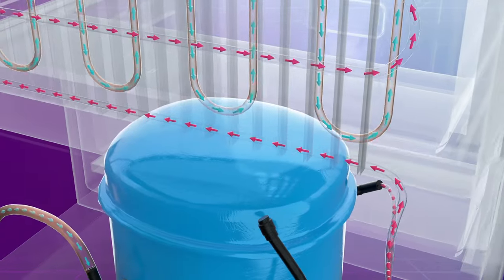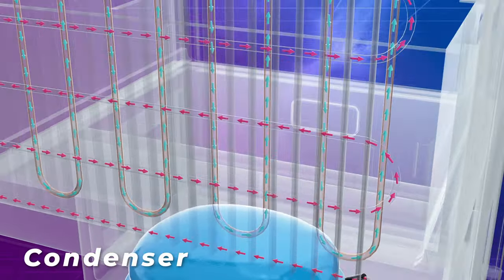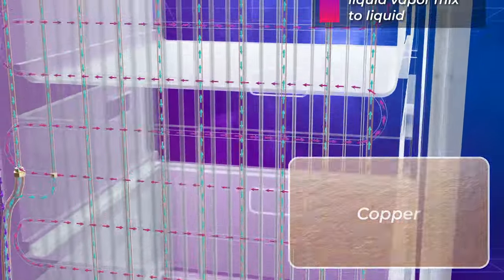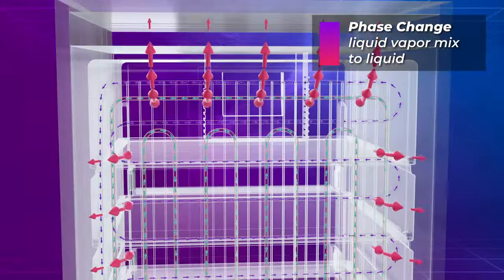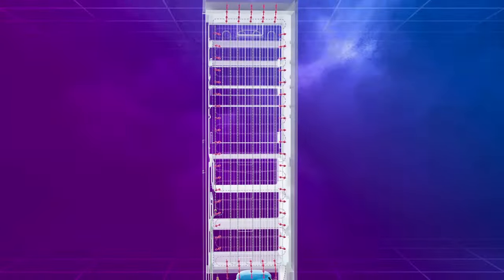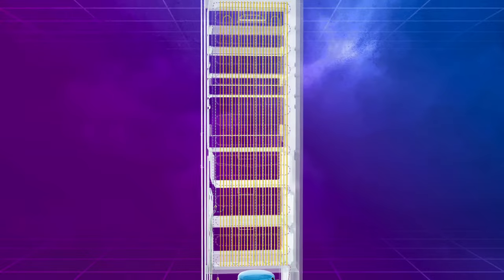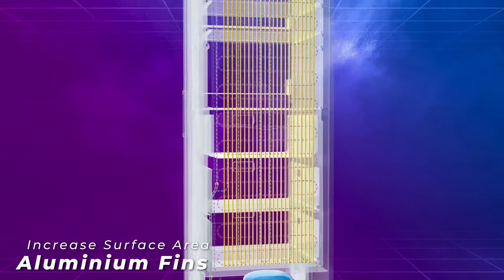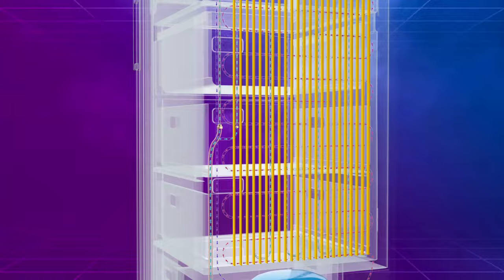Next, the refrigerant moves through the condenser coil, typically made of copper, where it condenses into a liquid and releases heat to the environment. Aluminum fins increase the contact area with the outside air and increase the heat transfer.